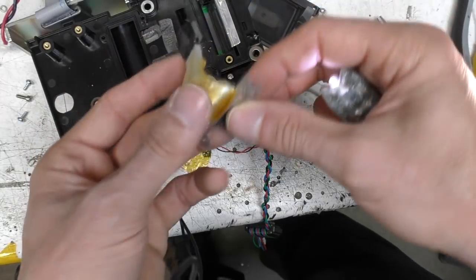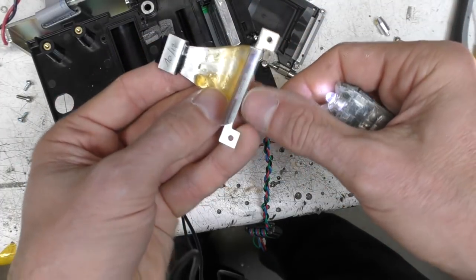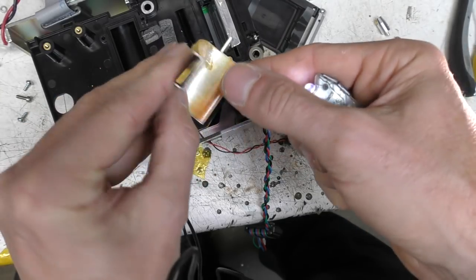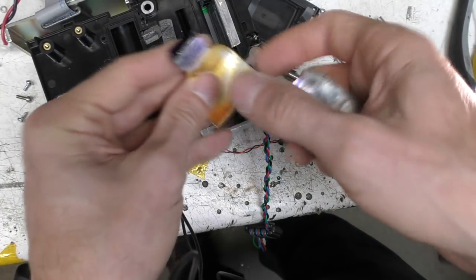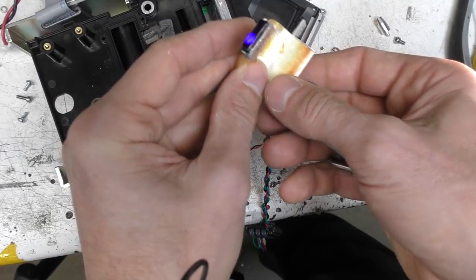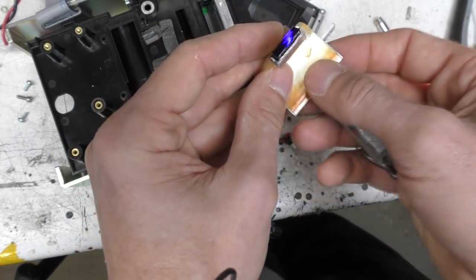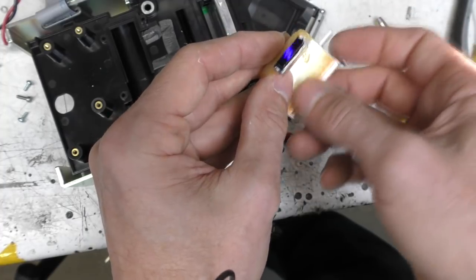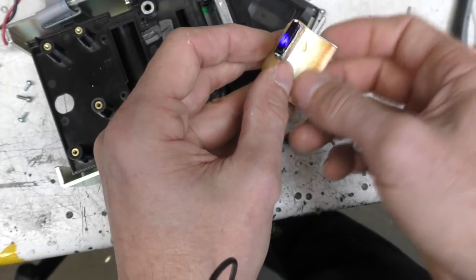And this is the fibre optic assembly. So this takes the line of fibres here and concentrates it down to the photomultiplier. If we shine light through, you can see there's also a blue filter on here, so that's obviously selecting the specific wavelength that the phosphor plate emits when it's excited by the red laser.